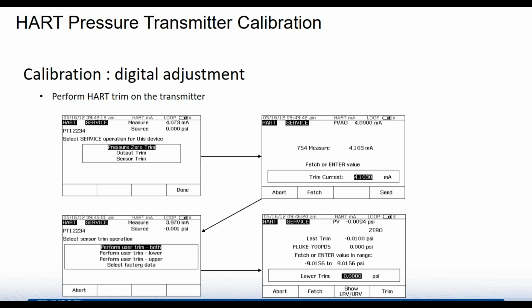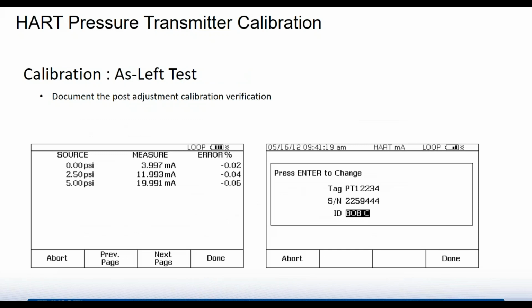Once you've finished making your digital adjustments through HART, now you can go ahead and repeat that test that you did to start for the as found, but now it's going to be the as left test. So this is the final test. Go ahead and do that, the same calibration procedure we talked about before. In this case, hopefully you've done your trim adjustments correctly and your results are within spec.